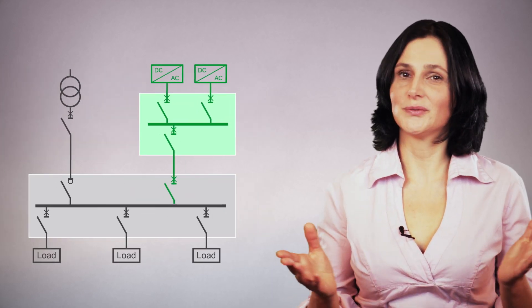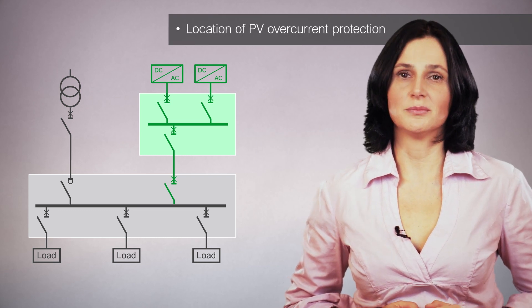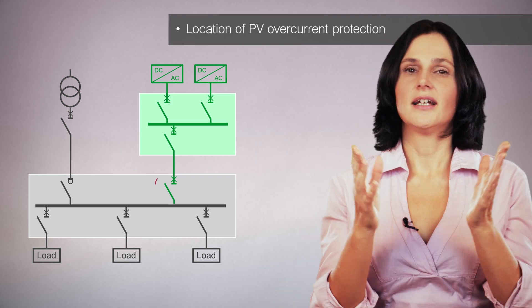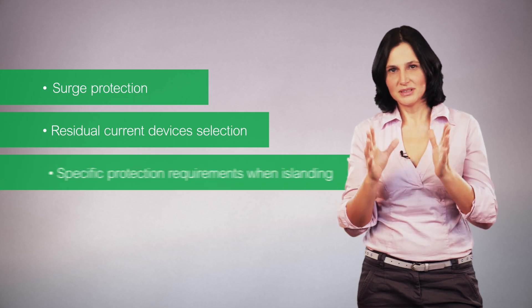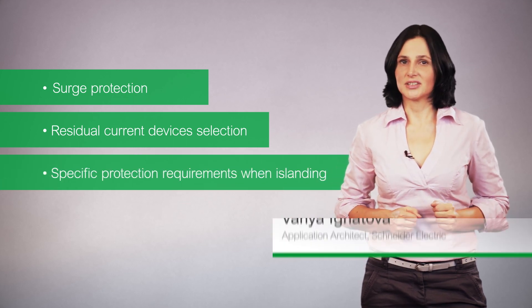To sum up, certain specific safety measures are required on the AC side of installations with photovoltaic production, including loss of mains protection, overcurrent protection for the photovoltaic power supply system which must be located on the building bus bar side, and AC isolation and switching for the photovoltaic system. In our next videos, I will cover additional protection measures such as surge protection, residual current device selection, or specific protection requirements for installations operating both grid-connected and off-grid.